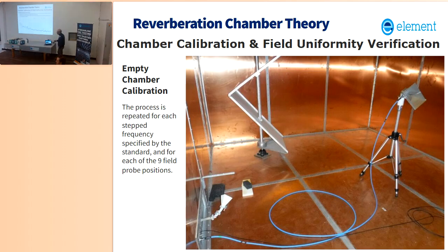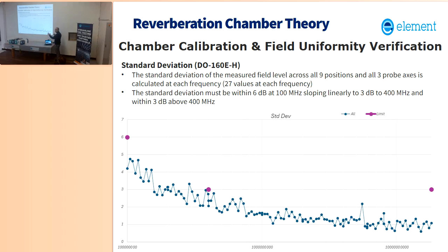How often do you have to do it? So the standard says that when you first build the chamber, you have to verify the field uniformity. You have to make sure that the treatment on the walls, the material on the walls, the size, the shape of the chamber, you get the field uniformity requirement. And then if you make any major modification, like say you go from galvanized steel on your walls to copper on your walls, or you go from a vertical tuner to a horizontal tuner, something like that, you have to redo the chamber calibration.